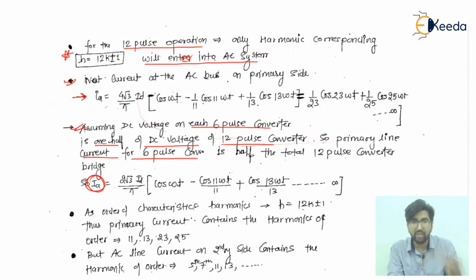So how are we actually deciding which frequency or which harmonics are going to be added, because these are in the form of Fourier series? So how do we decide whether it should be 12, 13, or 11? Read this point: the order of characteristic harmonics are of the type h is equal to 12k plus minus 1, as we have discussed in the first point also.